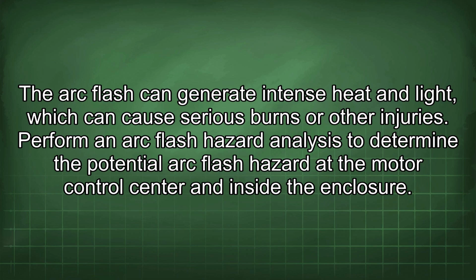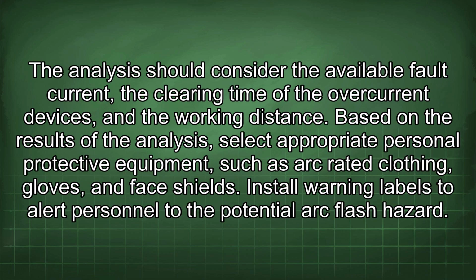Perform an arc flash hazard analysis to determine the potential arc flash hazard at the motor control center and inside the enclosure. The analysis should consider the available fault current, the clearing time of the overcurrent devices, and the working distance. Based on the results of the analysis, select appropriate personal protective equipment, such as arc-rated clothing, gloves, and face shields. Install warning labels to alert personnel to the potential arc flash hazard.